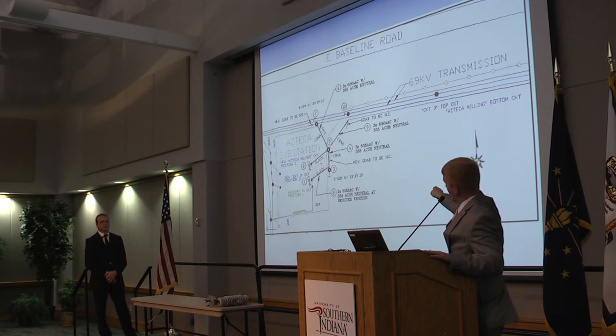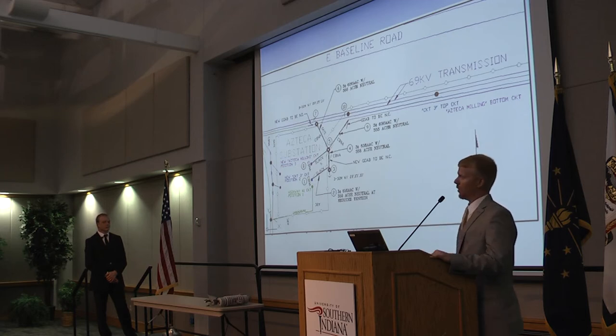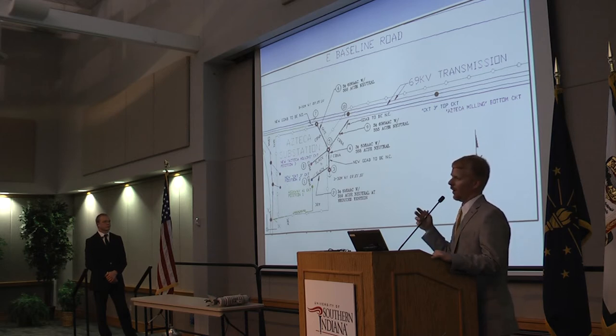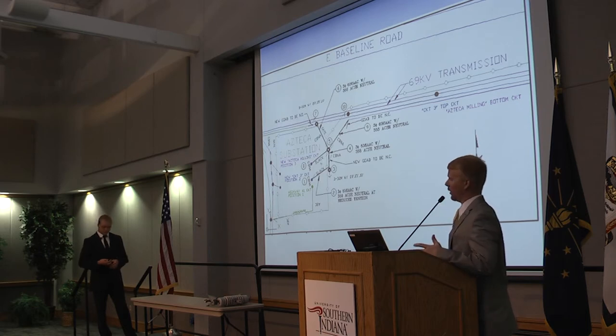The reason I don't have any guy wires here, these are slack span, which means that the only tension on that cable is from the weight of the cable itself. We use a pole loading program to test that. And from that pole loading program, that's where these numbers come from. It's an Excel program that Vectren purchased, which is very beneficial when looking at areas like this.